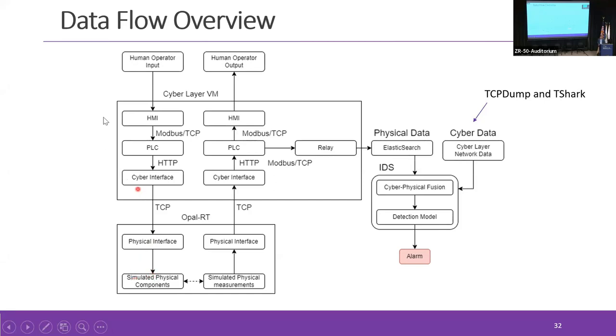So as I said before, the human operator here can give a command to open a circuit breaker. This command will go through Modbus TCP to the PLC. Modbus TCP is a communication standard that is used specifically for industrial control, and in this example it's used in our power system. So we'll carry this command from the HMI to the PLC, and then the command will be sent from the PLC all the way to the specific switch, for example, to trip it on or off as you desire.